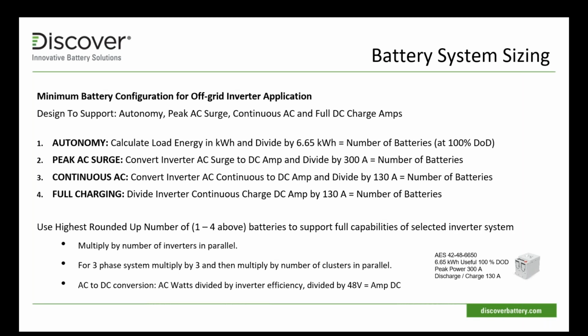but if they're included as well as an inverter charger, you need to add them into the total amount of energy being delivered to the battery. So if the charger and inverter is 100 amps and the solar charger is giving 50 amps, your total input to the battery would be 150 amps. So that is an important sizing of the system.